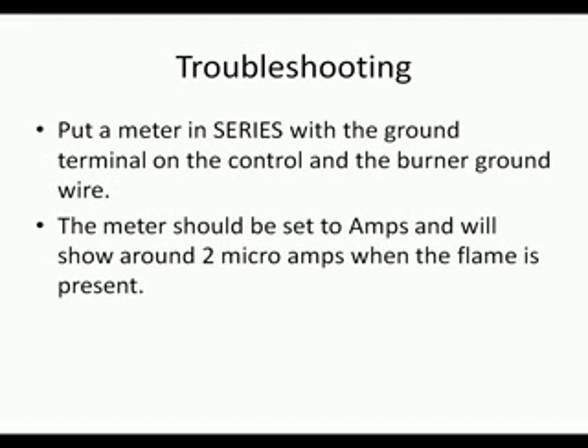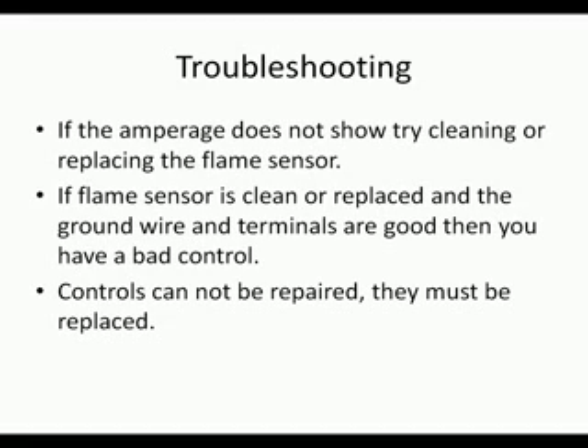For hot surface ignition, check the control wire between the control and the flame sensor. Replace the ground wire again to the burner assembly, control, and flame ground. Try putting a meter in series with the ground wire on the control and the burner ground wire. The meter should be set to microamps and will show around 2 microamps when the flame is present. If the amperage does not show, try cleaning the sensor or replacing the flame sensor. If the flame sensor is clean and replaced and the ground wire and terminals are good, then you have a bad control. Controls cannot be repaired in the field, they must be replaced.